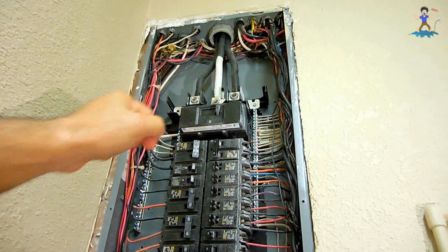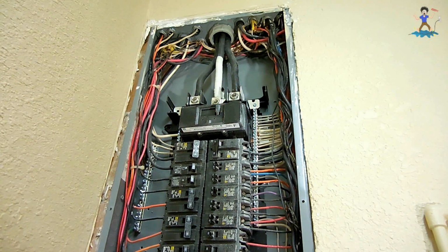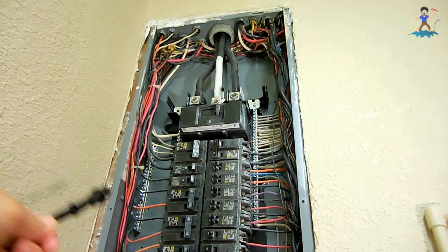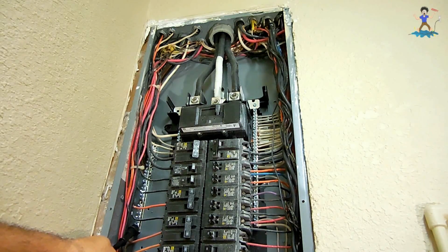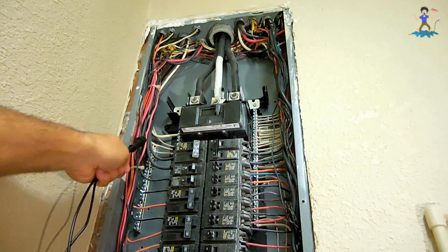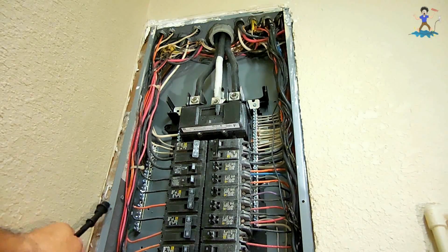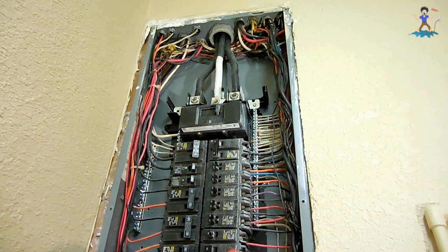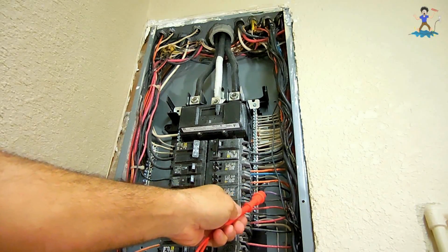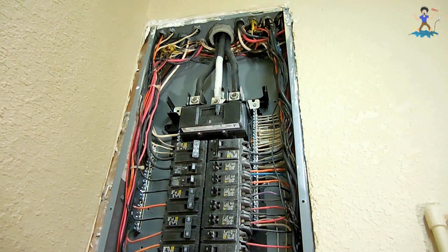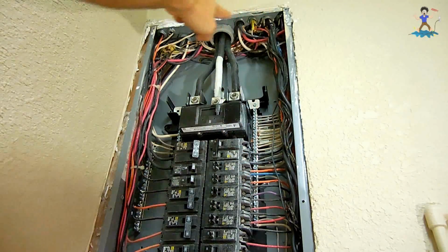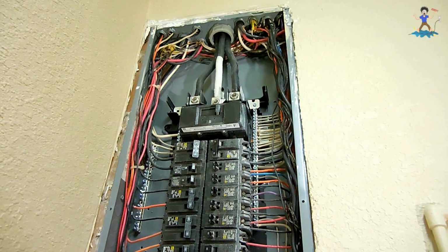Once that's complete, you're going to take the black test lead from the Megger and connect it to the ground bar inside the breaker panel or to the breaker panel enclosure itself. You're then going to take the red lead and connect it one at a time to each one of the wires inside the conduit which was connected to the circuit breaker. When you take the readings, you're going to compare the readings on each one of those wires. They all should be very high readings.